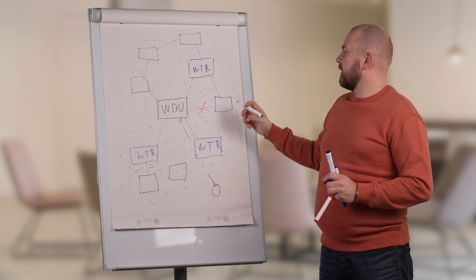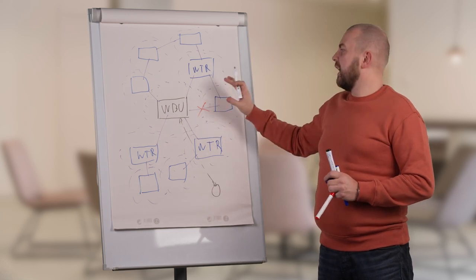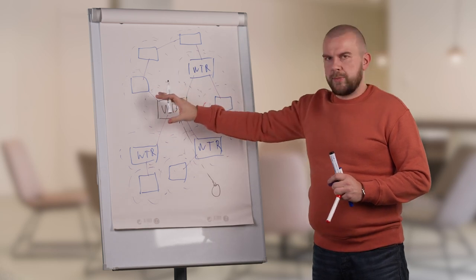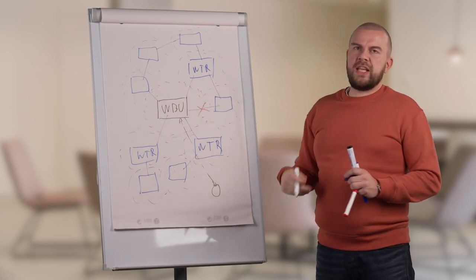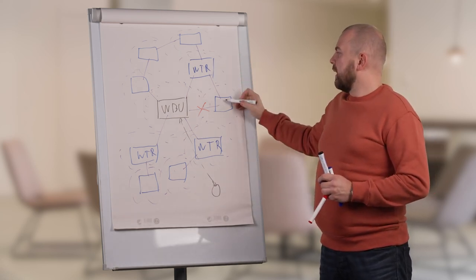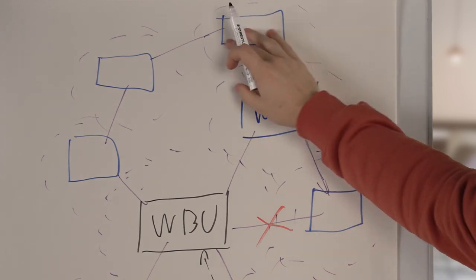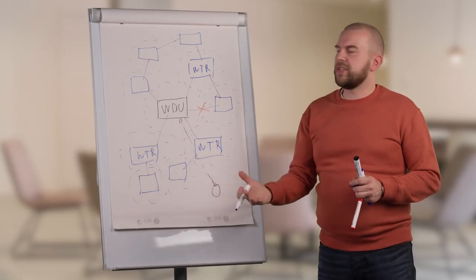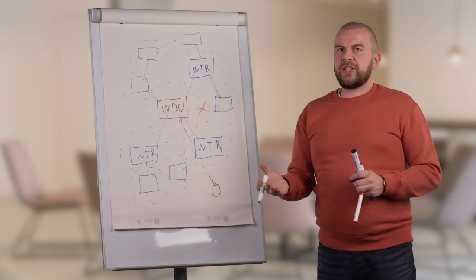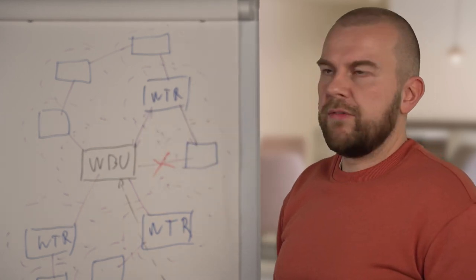Each transmitter has a main connection that it is using, selected based on signal quality and connection factors. But each transmitter always keeps a list of other nearby connection points. For example, a WTR connected to one node always knows what other transmitters are in its coverage area. If the primary connection fails, the second-best connection point — such as the WBU itself — can be used instead.